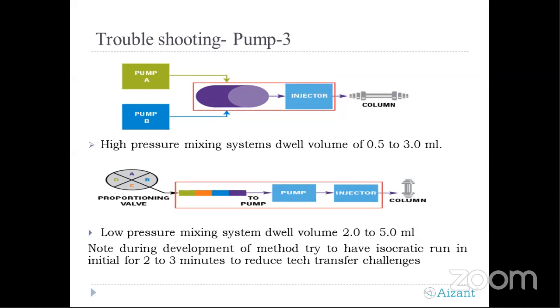But now, with the advancement in the systems, there are quaternary pumps we can use, but it's a low pressure gradient in which all the four pumps, based on the gradient, will pump the solvent. It will be mixed in the mixer and then pumped with the injector to the column. And there is a dead volume of 2 to 5. In high pressure, it will be 0.5 to 3 ml, and in low pressure, it will be 2 to 5.